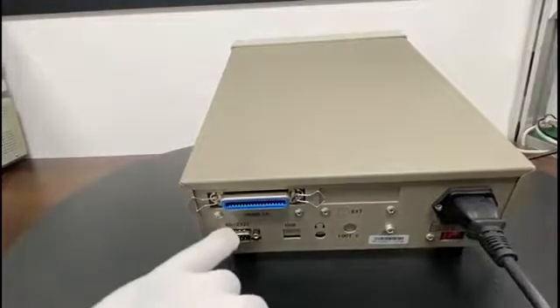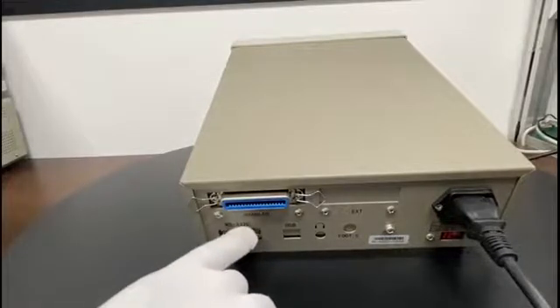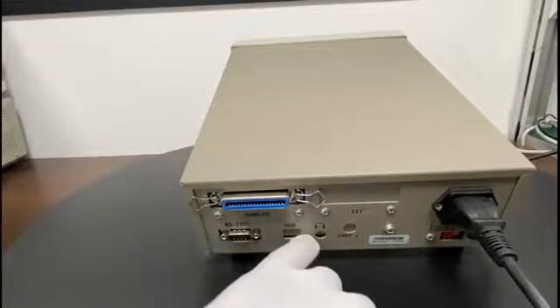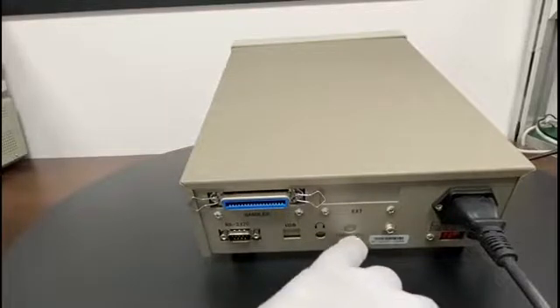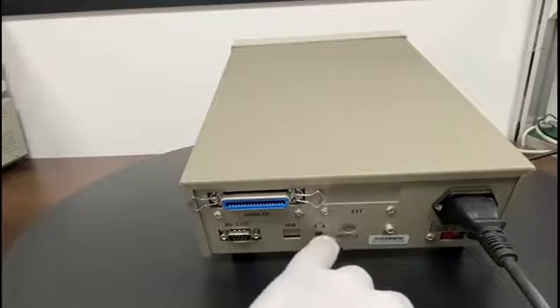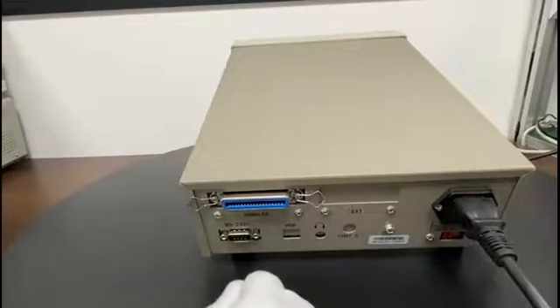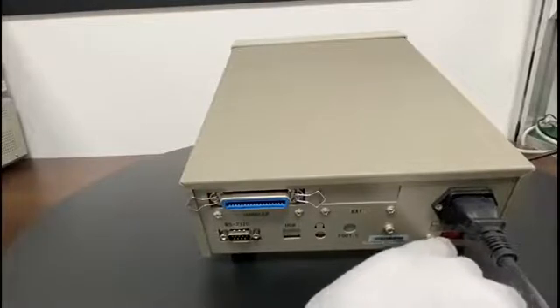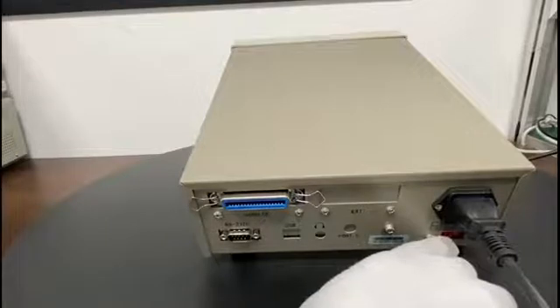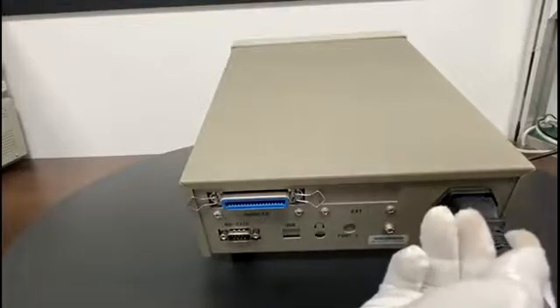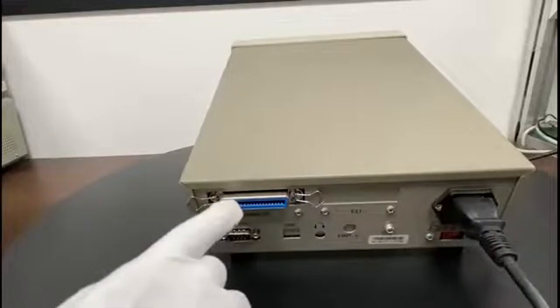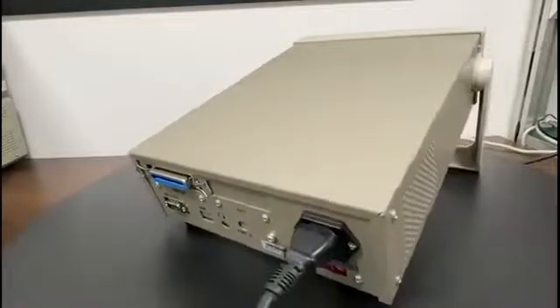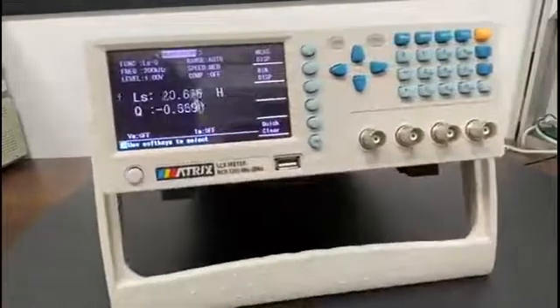Let's see the rear panel in the back. Here you can see RS-232 port and here is the USB device port, the USB host port, and the handler port. Here you can see the power supply switch which is switchable 110 volt and 220 volt. Here is the power supply socket and here is the handler sorting interface.